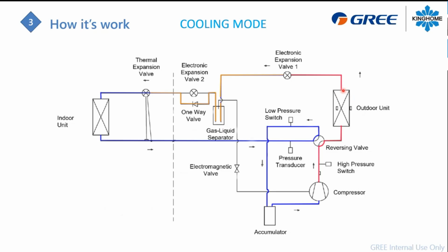And then at the outlet of the condenser, you will hit the first electronic expansion valve. This valve will manage the refrigerant just to make sure you have 100% liquid refrigerant after your condenser. So after that valve, you will be 100% liquid. We're still in the outdoor unit, but it's gonna fill up a gas liquid separator. So you will have one cylinder right here, the pipe going down in that cylinder, and on the other side, you will pump only the liquid. So you still have 100% liquid refrigerant in that cylinder. It's going to flow across a one-way valve. So this is a check valve right here.